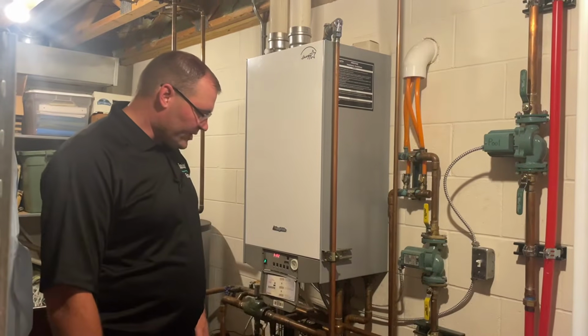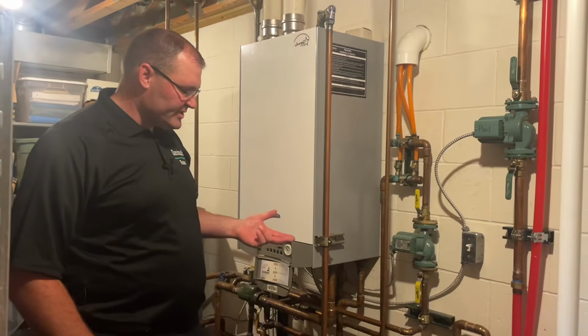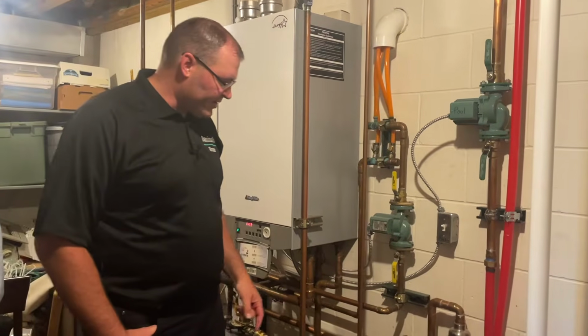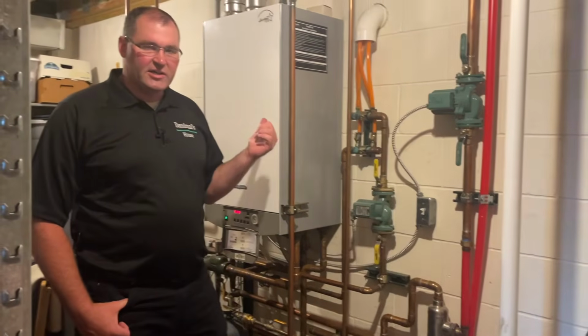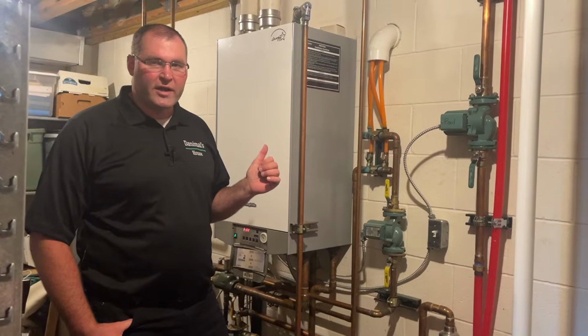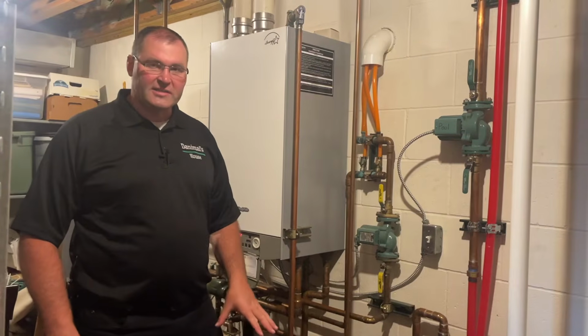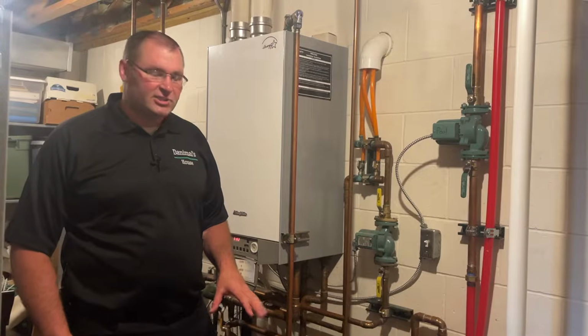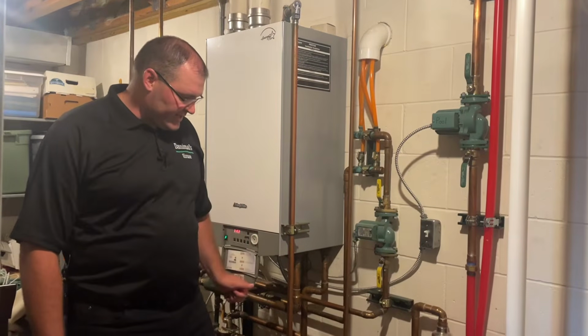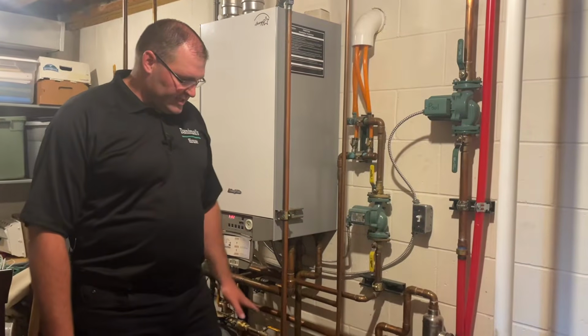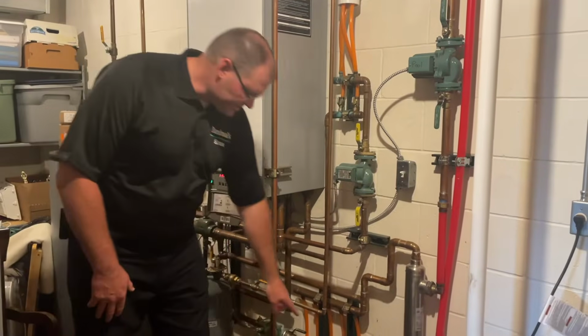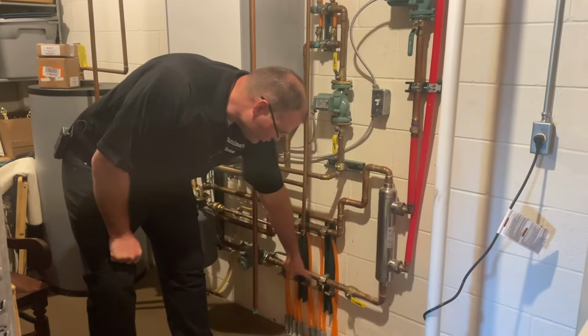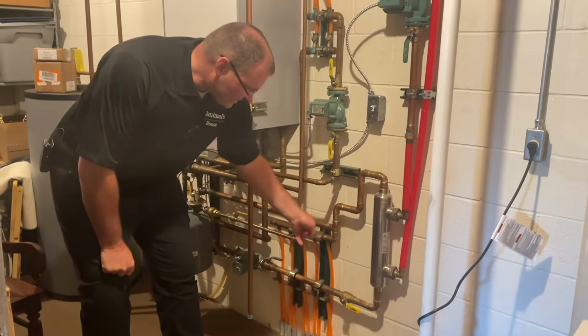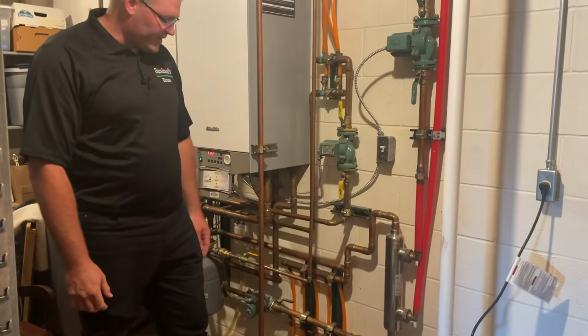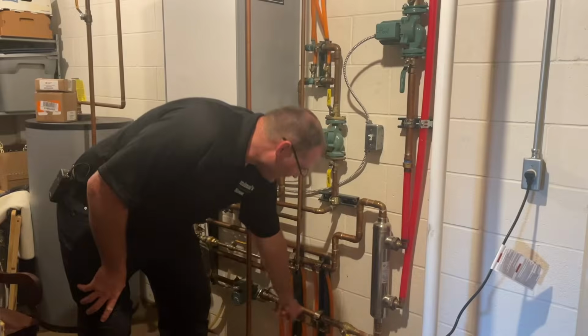This is a 2-zone system with primary secondary piping. Normally you'd have 110 to 120 degree water going down to the floor because concrete can only handle about that much. But in this case, I'm stealing a partial part of the loop — I closed off my basement loop and made a little extra path for the water to go through, closing it off here and allowing it to go here.